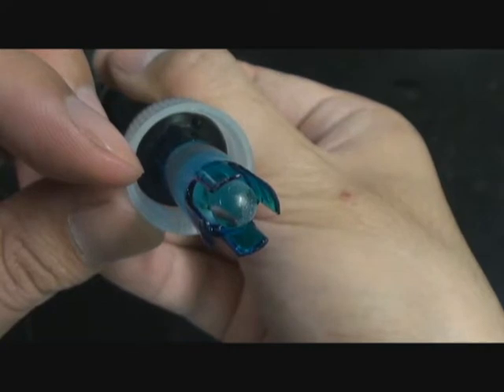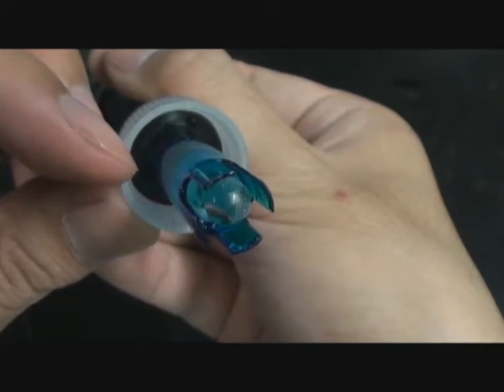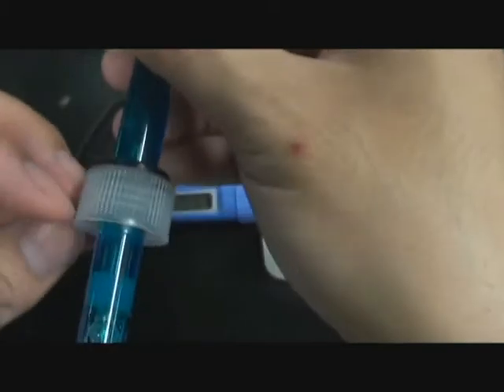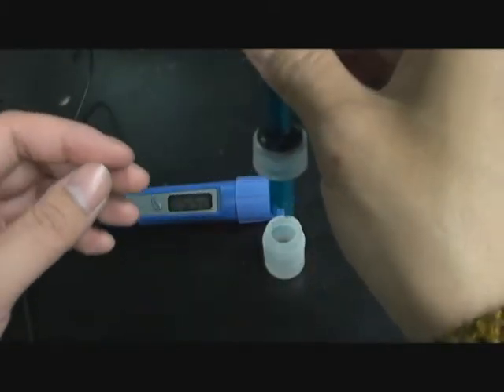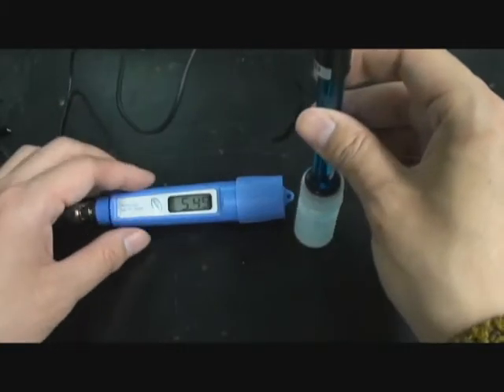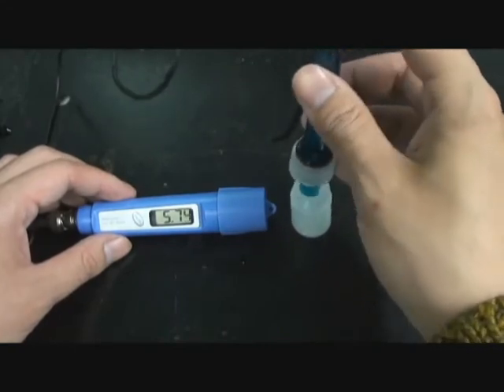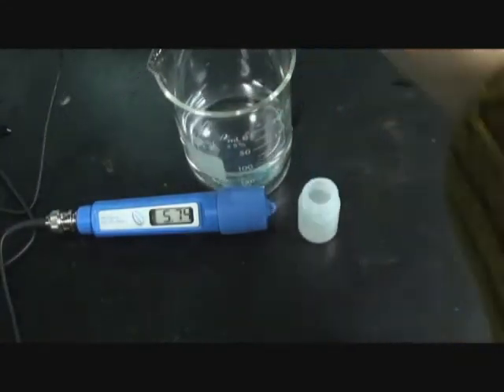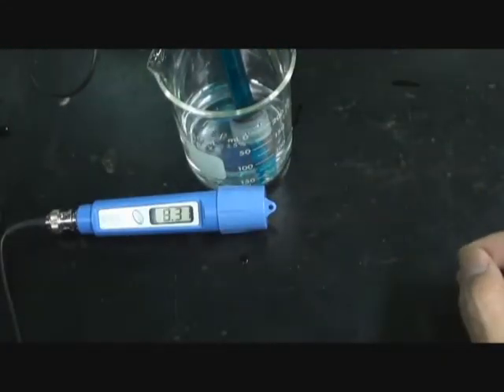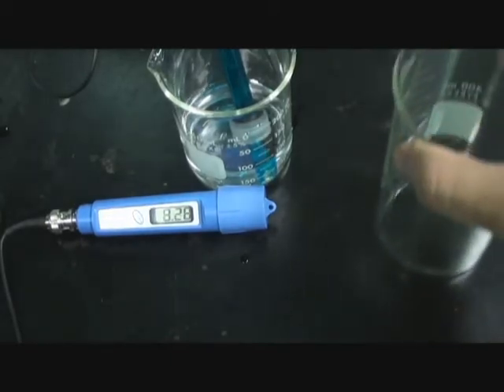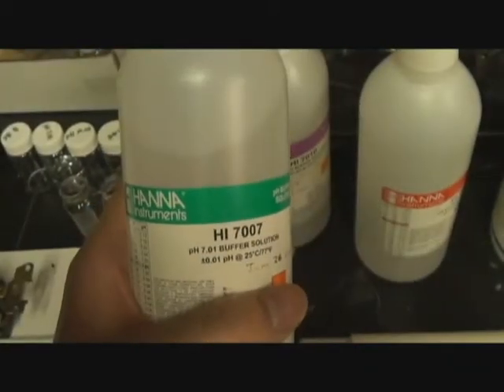For the glass electrode to work, you must immerse the electrode all the way up to this reference electrode. Otherwise, you'll get erratic and irreproducible readings. Now I'm going to dip the electrode into some distilled water to wash off the storage solution. So let's start taking measurements. But before we can do that, we have to calibrate the electrode.